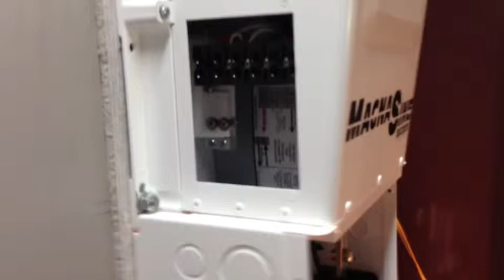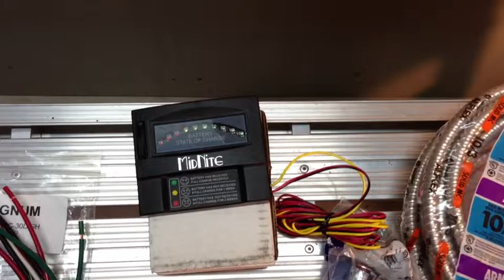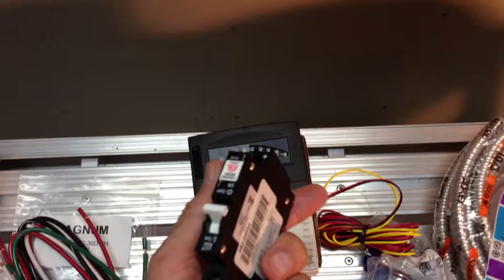Next thing I'll install is this, a MidNite Solar state of battery charge meter. I'll put that in, and that's going to go over here on the side wall somewhere, I think we talked about this before. It also connects to battery plus and battery negative, and it needs a fuse or circuit breaker, so I'm going to put in a 2 amp circuit breaker, and it will also go onto the DIN rail, which still leaves me the 2 additional slots we were talking about.